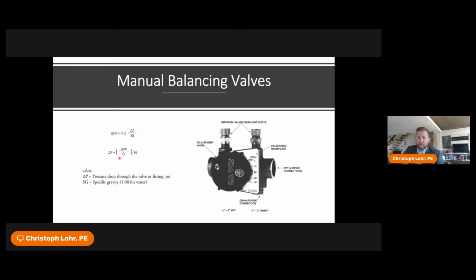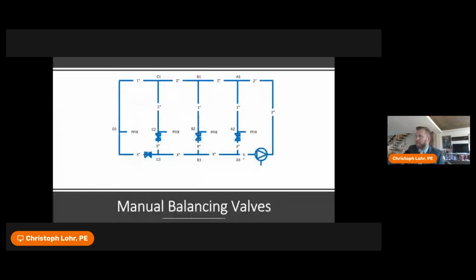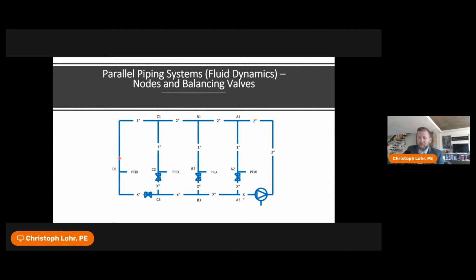When these systems are not balanced, you can get a lot of issues in terms of flow not going to where it should go in the system. When utilizing these valves, anytime the system is commissioned, there has to be balancing done on the system. And the balancing isn't just a once through. Every single time you have a change in pressure, you're trying to get a delta P, not a P. So that delta P, if we go back to our previous slide, is across each one of those valves. And so we have to determine what the artificial pressure drop is across each one of those valves. So often it requires the balancer to go back and forth between valves.